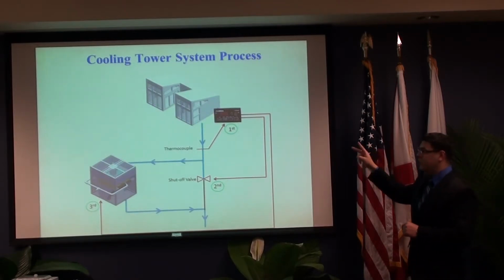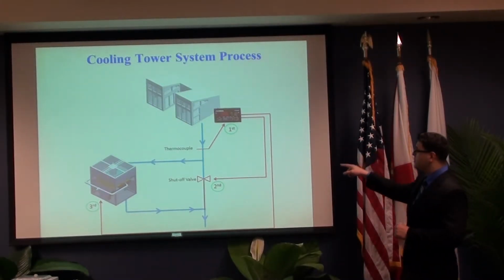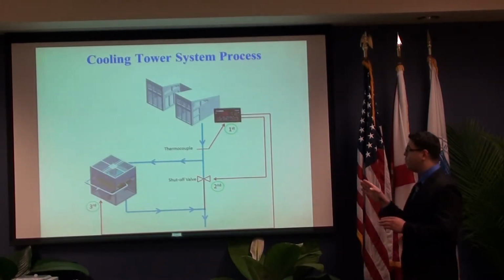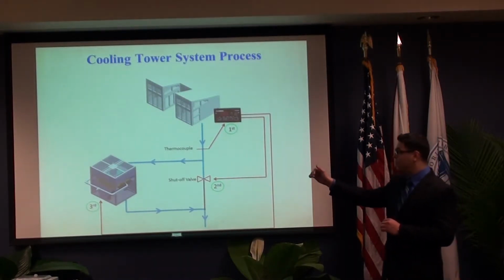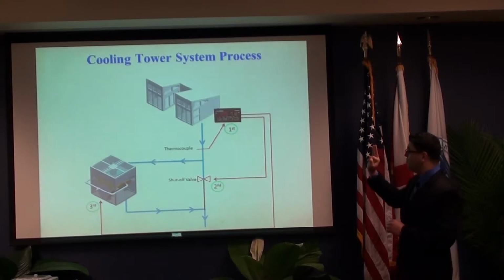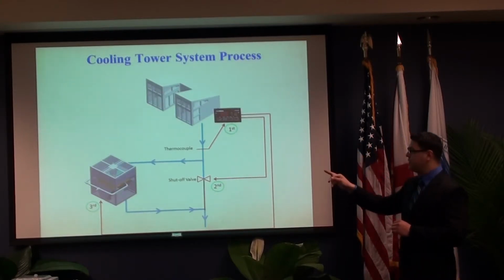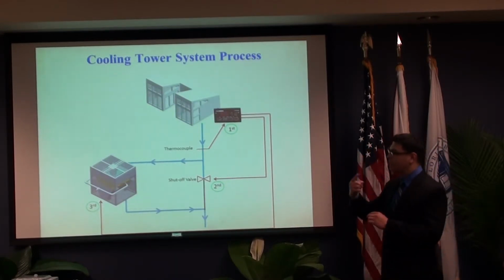The thermocouple is going to read that water temperature and send that signal straight to the thermal controller, and the thermal controller is going to send out 2 more signals. The second one is going to be to the shutoff valve to redirect the water to go towards the dry cooling tower, and then it's also going to send a third signal to the relay of the motor on the cooling tower to turn on the fan.